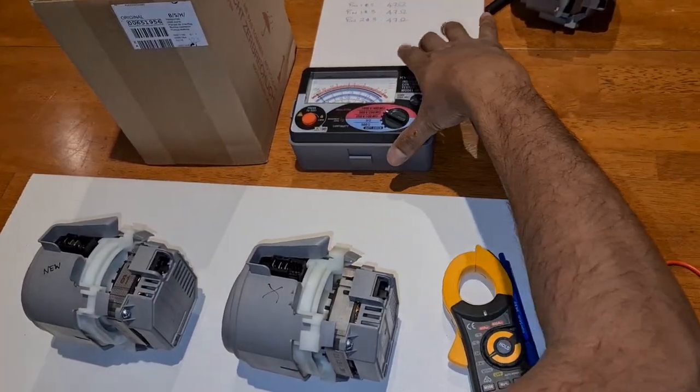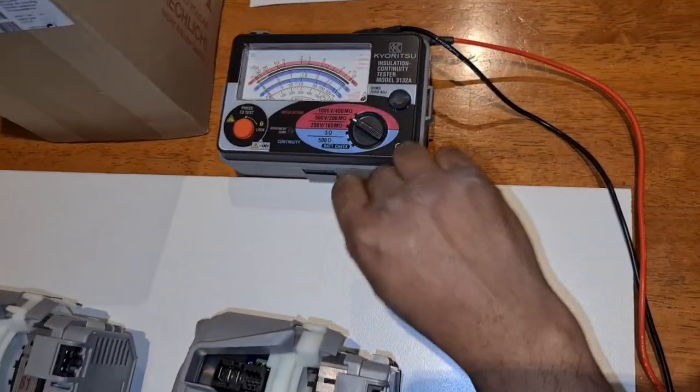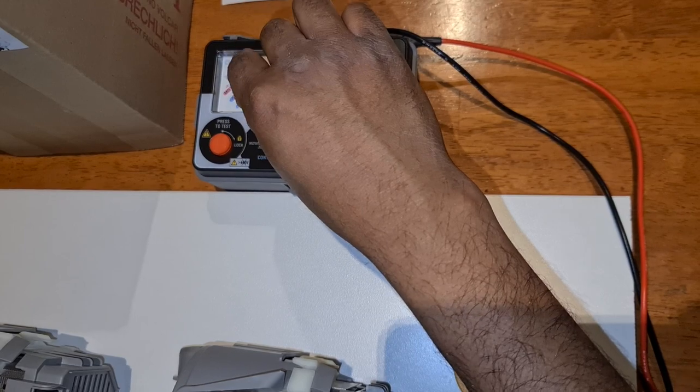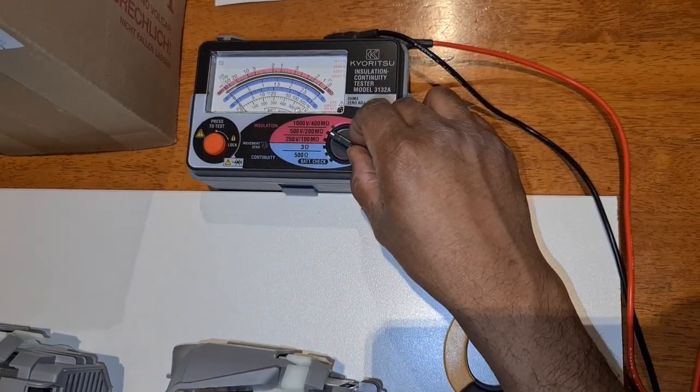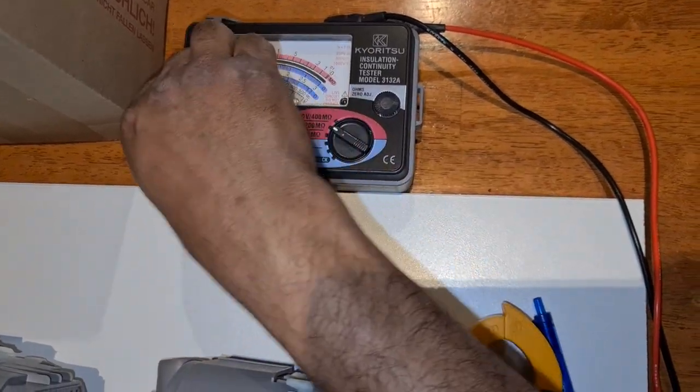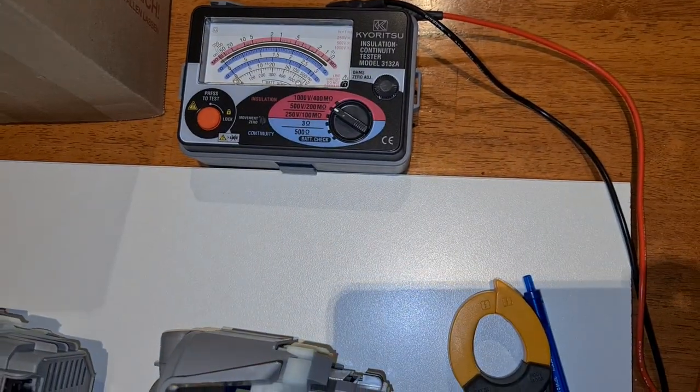So here we use another device. I use a Kyoritsu Insulation Continuity Tester to test the insulation resistance. Now we set the instrument at 500 volts, 200 mega ohms, and turn the yellow knob to the lock position.